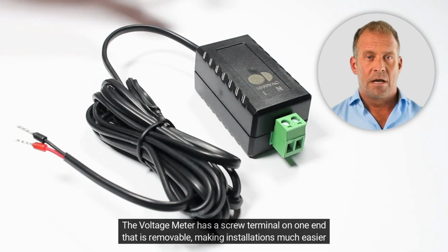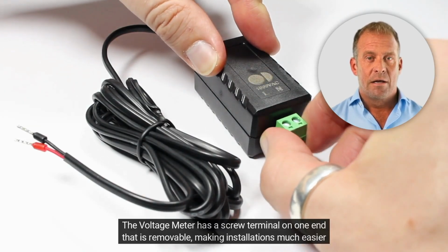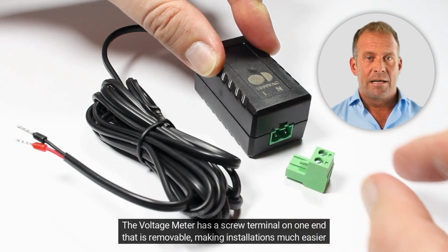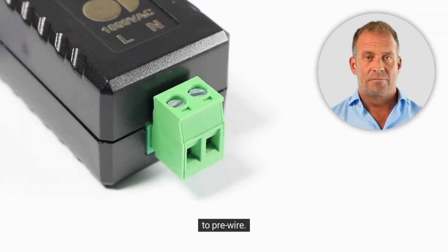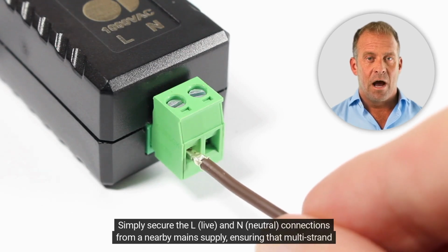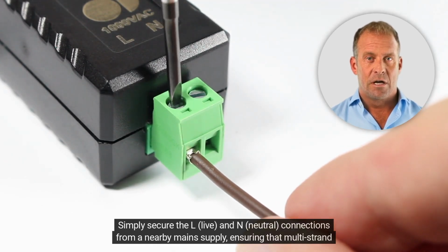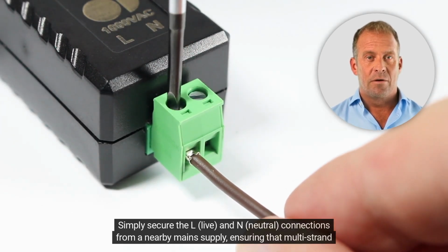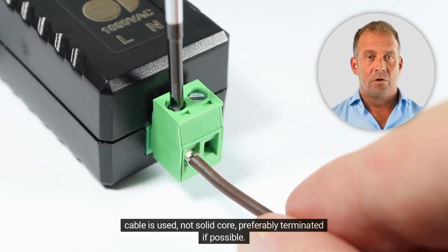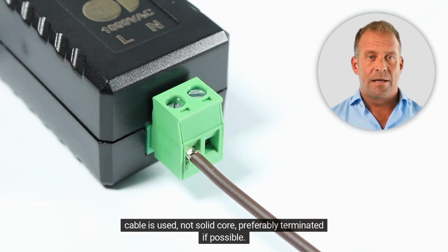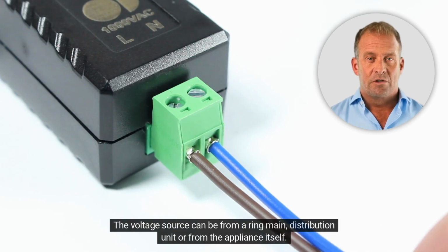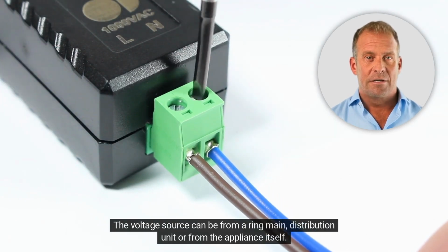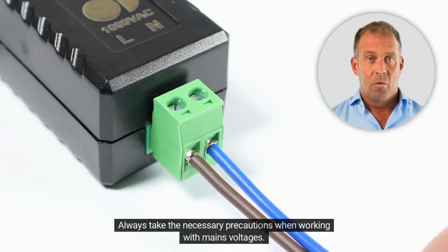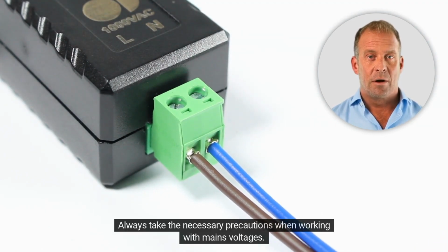The voltage meter has a screw terminal on one end that is removable, making installations much easier to pre-wire. Simply secure the L, live, and N, neutral connections from a nearby mains supply, ensuring that multi-strand cable is used, not solid core, preferably terminated if possible. The voltage source can be from a ring main, distribution unit, or from the appliance itself. Always take the necessary precautions when working with mains voltages.